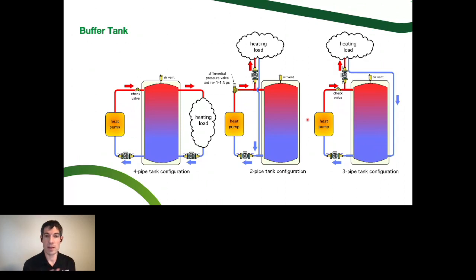And then modulating condensing boilers just got really good. The turndowns got really low. So people were saying, wow, we don't need buffer tanks anymore. And now it's kind of coming back, the pendulum swinging again, because heat pumps are saying, no, we want to have a buffer tank again. So we need to figure out how to size and pipe these things again.